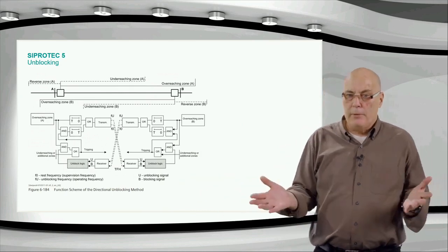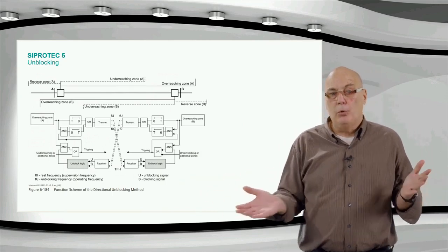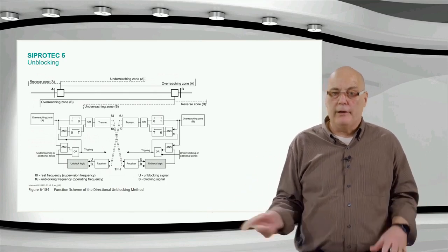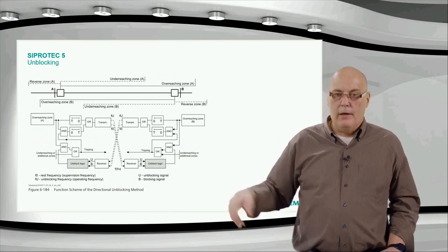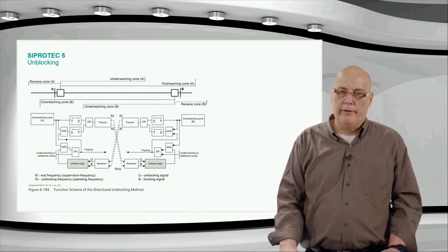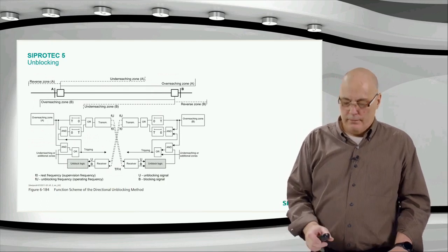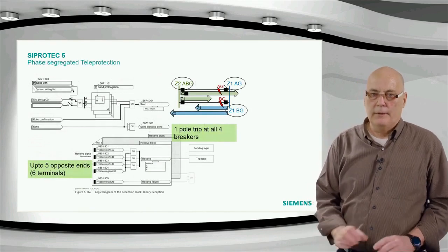The F0 has disappeared, I'm receiving nothing, I'm not receiving FU or F0, channel failure. It'll give you a channel failure alarm, and the logic will deal with the communication failure. That's just a different technique of doing it. That is a different receive block as such.